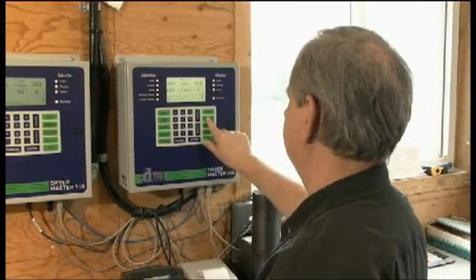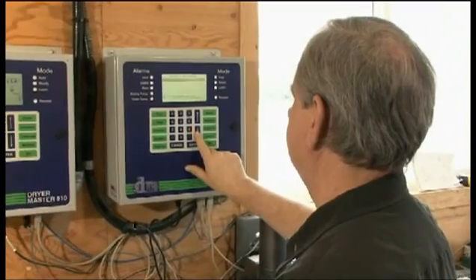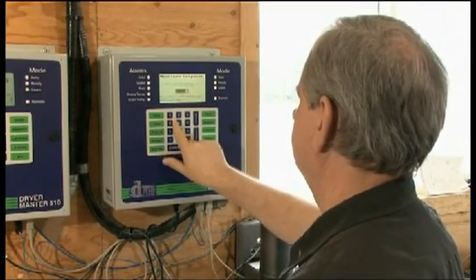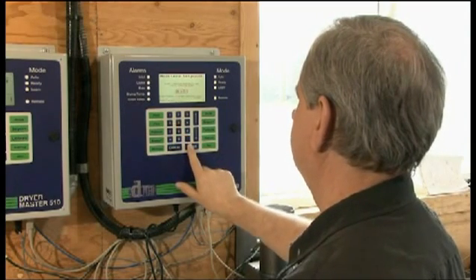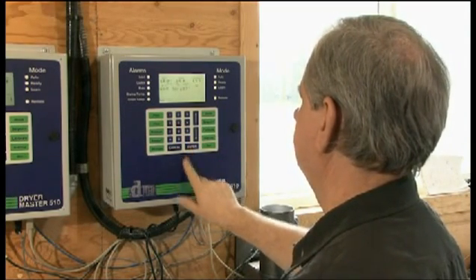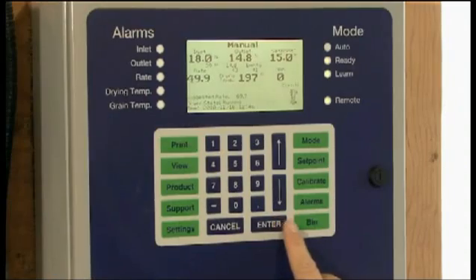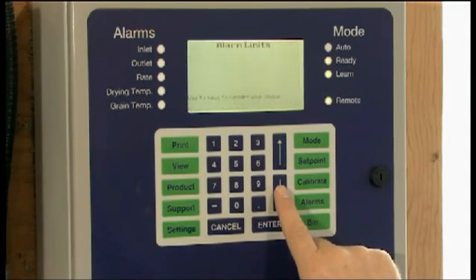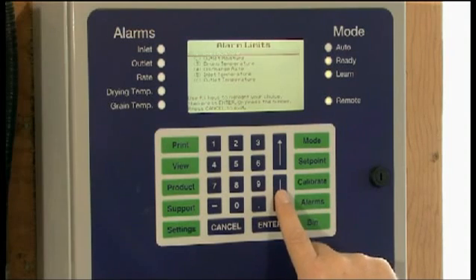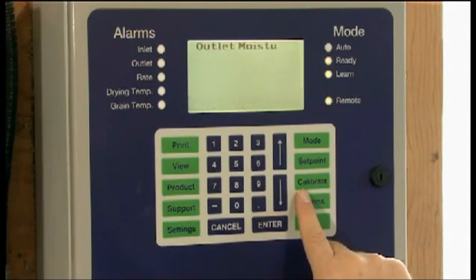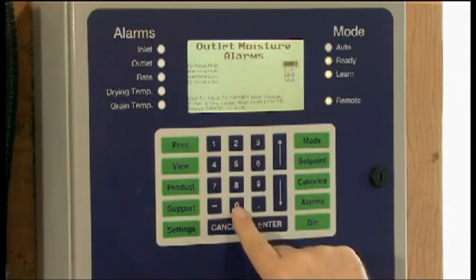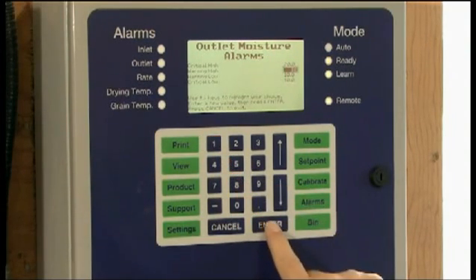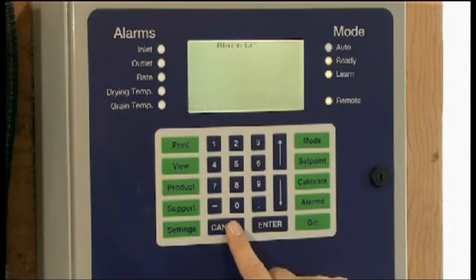The moisture sensors, sampling button, and air temperature sensor are all wired to the Dryer Master 510 panel, which becomes the new workstation for the operator to monitor and control the dryer. The operator can view online information on the Dryer Master screen and use the panel to adjust settings such as alarm limits and moisture targets. Critical dryer functions such as starting and stopping, as well as setting the drying temperature, and any drying safety and interlocks are still handled by the dryer control system as before.